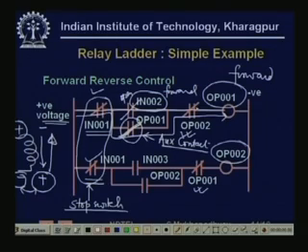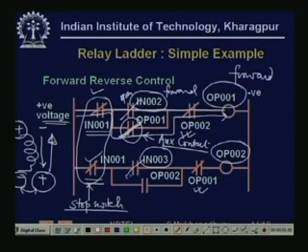Now in this position, while the forward coil is on, suppose somebody presses the backward coil or the reverse coil, what is going to happen? So then this will become on, but interestingly nothing will happen, this coil will actually not get supply because of this one, which is another auxiliary contact. So whenever this is on, this becomes excited and this becomes open. So this will be open, which means that even if this becomes on, the continuous path stops here because this is open. So therefore this cannot be excited while this is on.